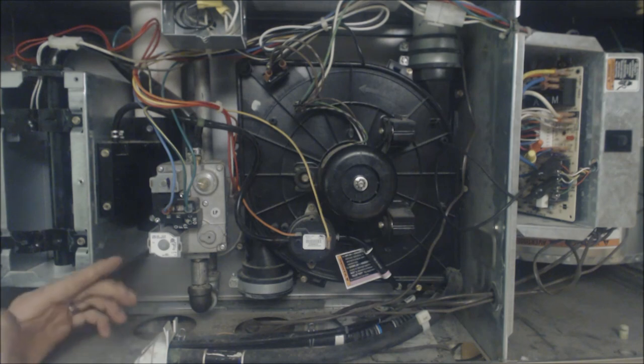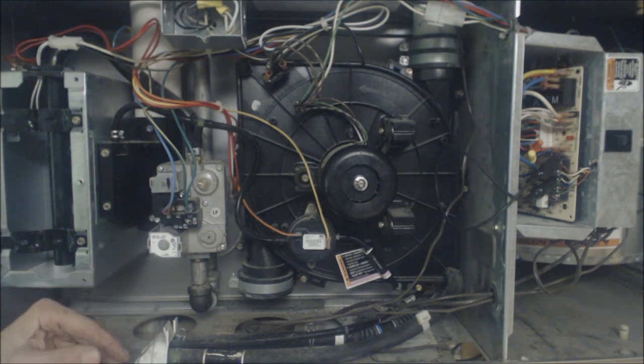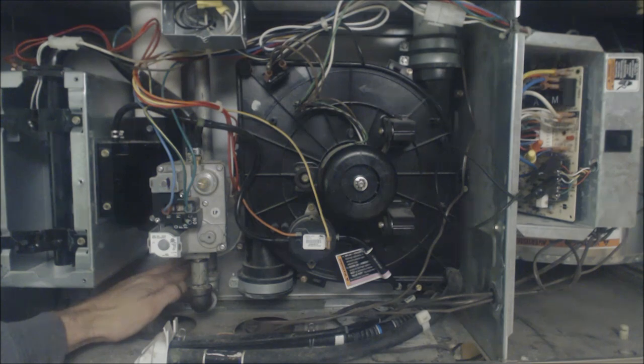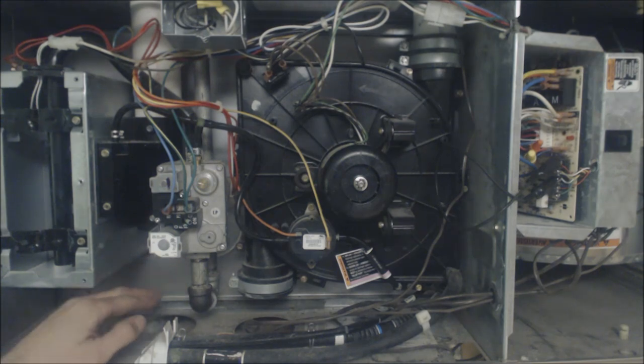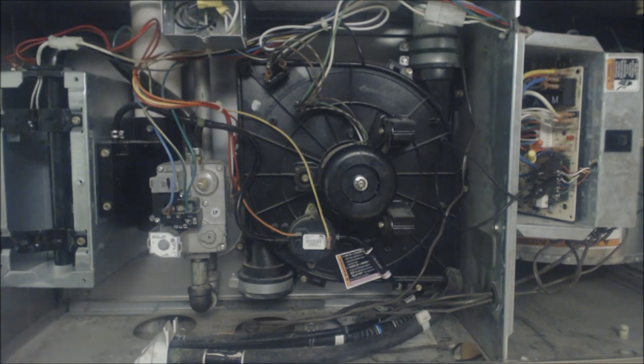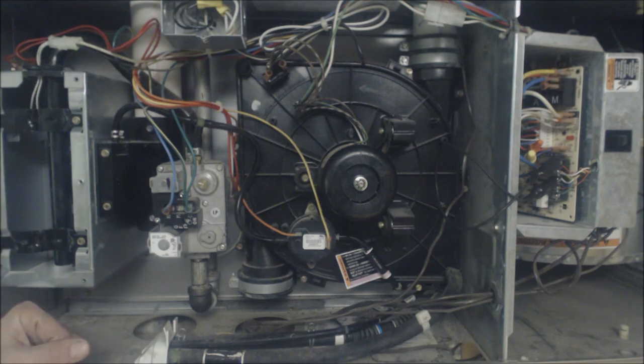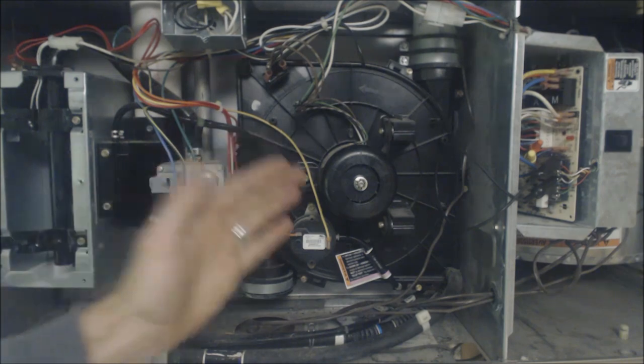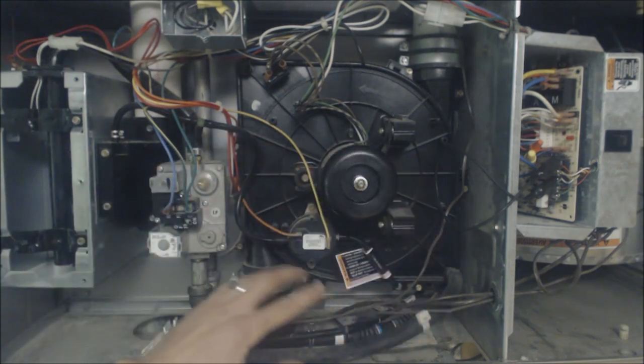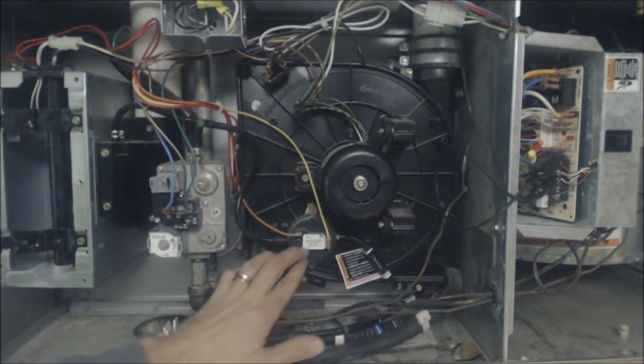Once it does that there's a blower on delay for about 20 seconds or so, it's waiting for the heat exchanger back here to warm up so it's not blowing cold air on the customer, then after that the blower motor will turn on and that is the sequence of operation.